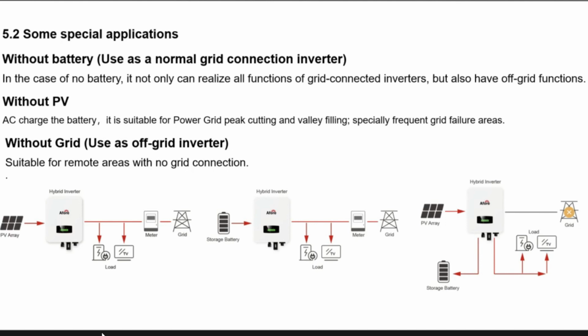Yes, that's the feature of a hybrid inverter. They can do both. Most hybrid inverters don't have that feature, and just the backup is working. But without a battery, I understand, if the grid is off, a lot of different suppliers don't offer off-grid without an initial grid connection. So they don't start without an AC coupling.